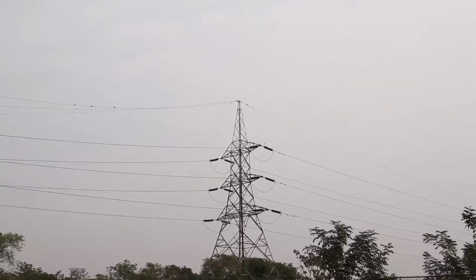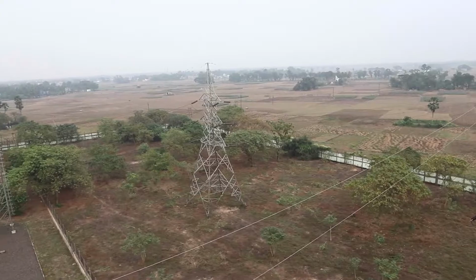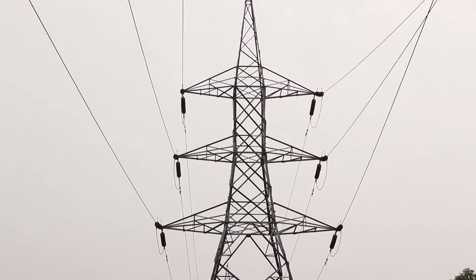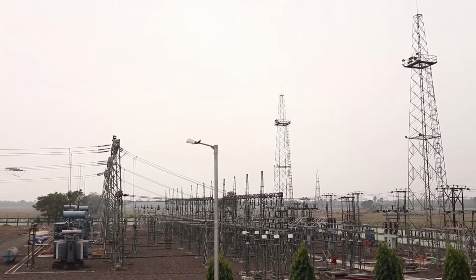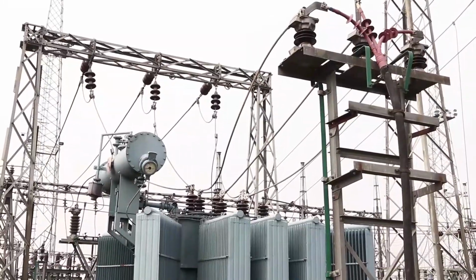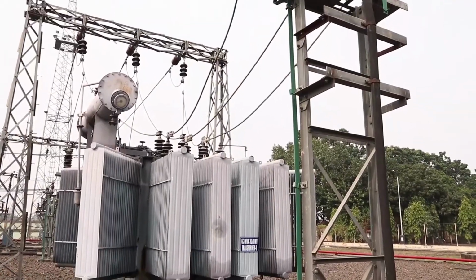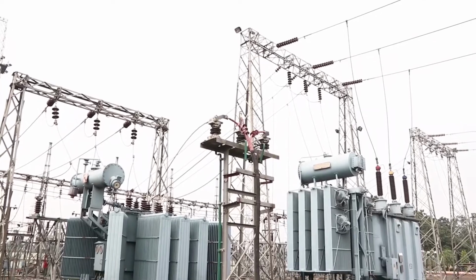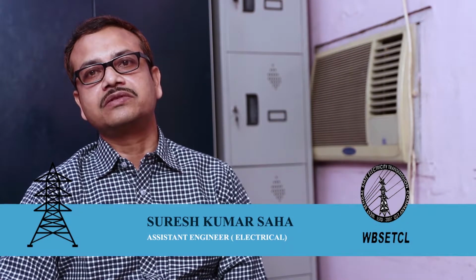This substation receives power from Arambagh 400 kV substation of WBSETCL through a 132 kV double circuit line. This is also connected to Belmuri 132 kV substation through a double circuit line. In normal situation, Belmuri 132 kV substation receives power from this substation. After receiving the voltage at 132 kV, it steps down the voltage to 33 kV through 3 numbers of 132 by 33 kV power transformers and delivers power at 33 kV through 6 numbers of 33 kV feeders. 33 kV voltage is also stepped down to 11 kV through 3 numbers of 33 by 11 kV power transformers and delivers power at 11 kV voltage level through 6 numbers of 11 kV feeders.